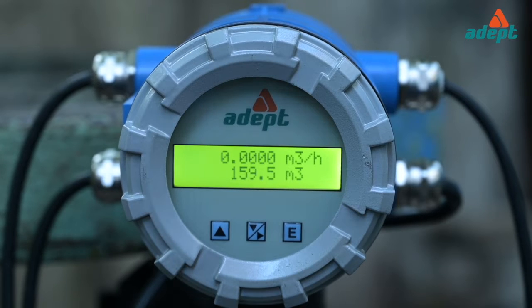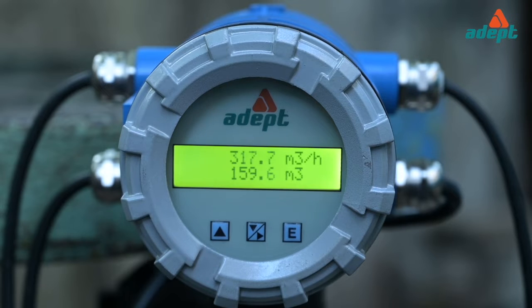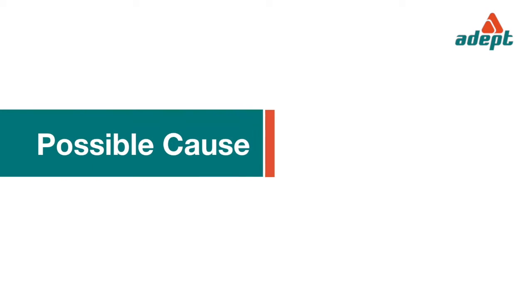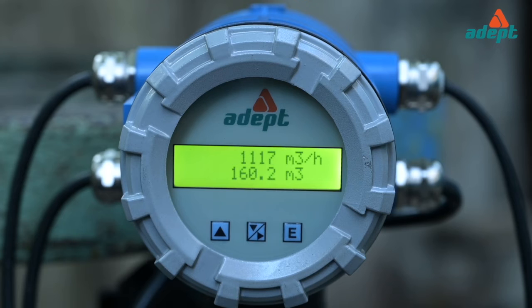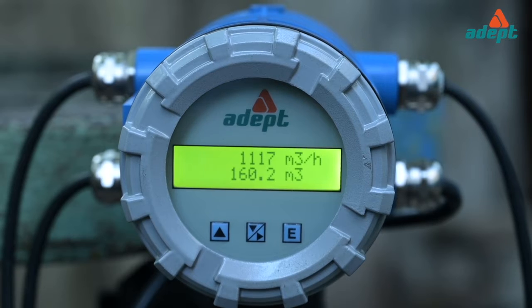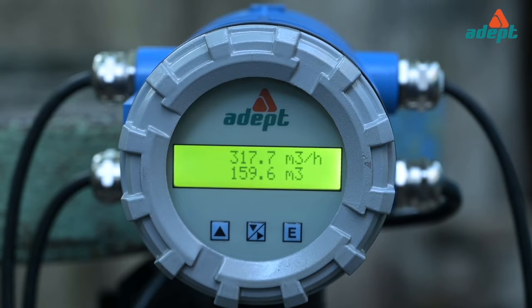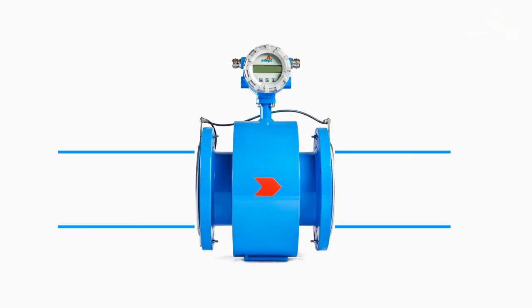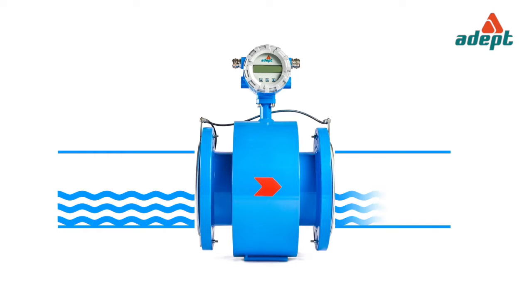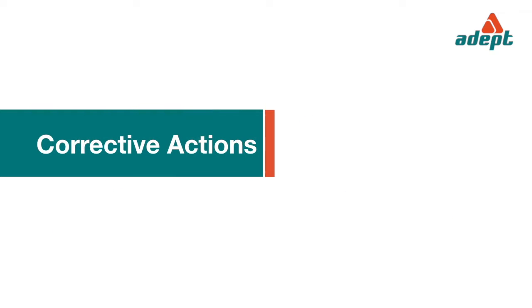Indicated flow rate drops to zero value intermittently and then recovers. Possible cause: the low flow cutoff level is not correctly set, or flow velocity is very low. Corrective action: reduce the cutoff level in small steps and check.